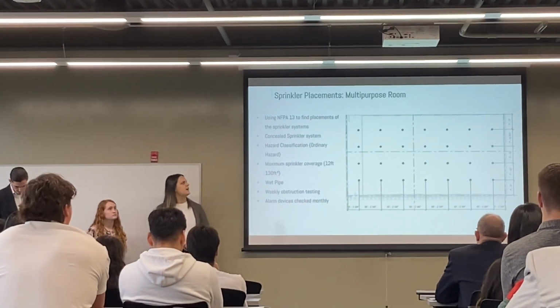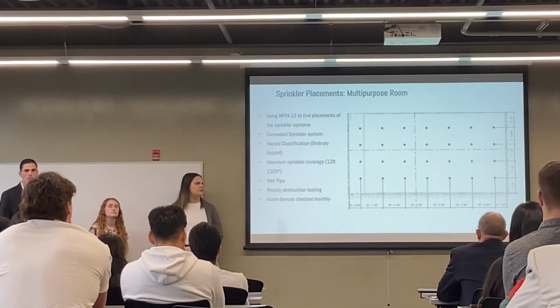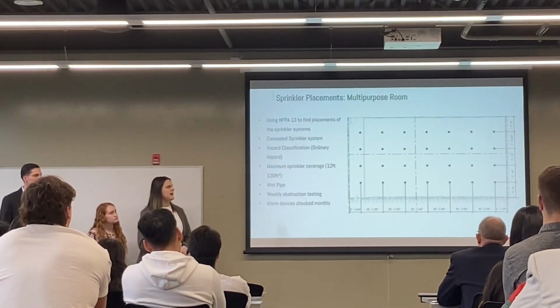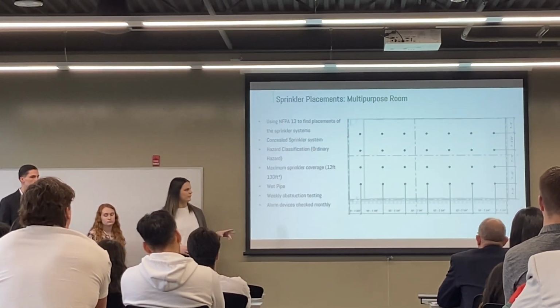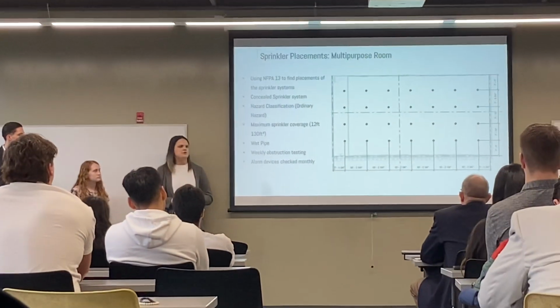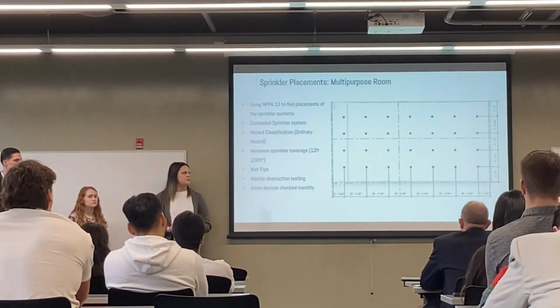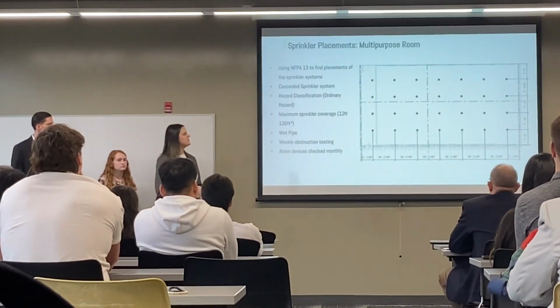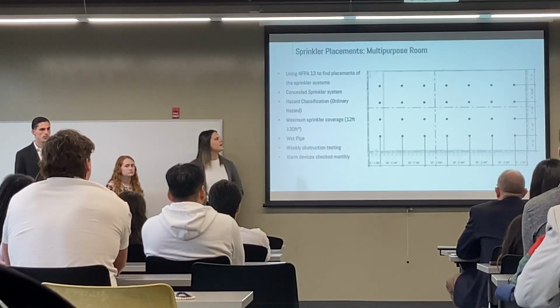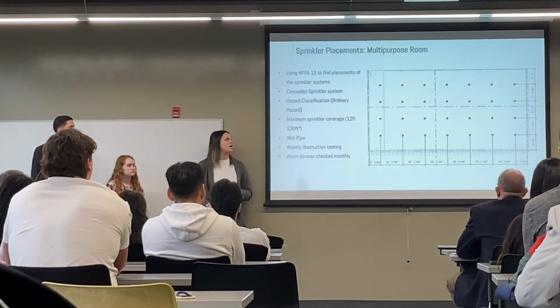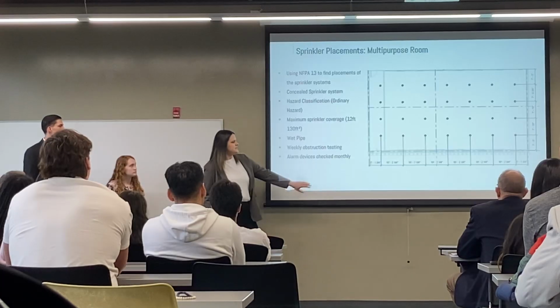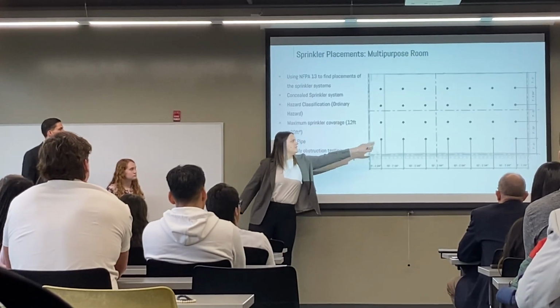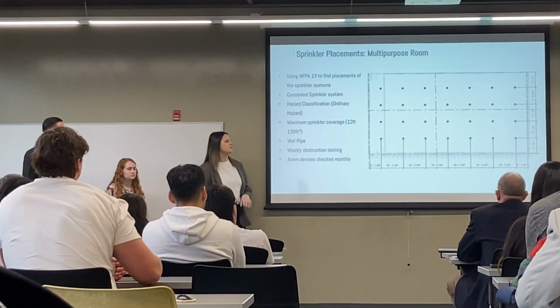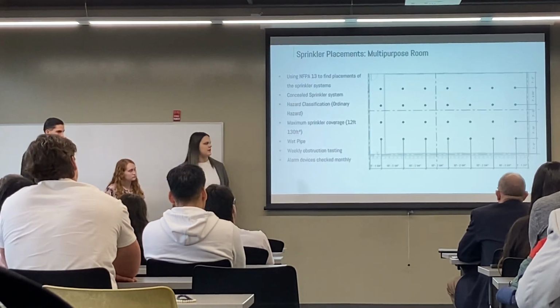And I used hazard classification Ordinary Hazard 2. I did this because of the size of the room, and because there's going to be a lot of mechanical equipment in this room, we just want to make sure everyone's staying safe. So that means that the maximum sprinkler coverage will be 12 feet or 130 square feet. So as you can see from this spacing, each of these fixtures will only have that 130 square feet. So that's how I space them.